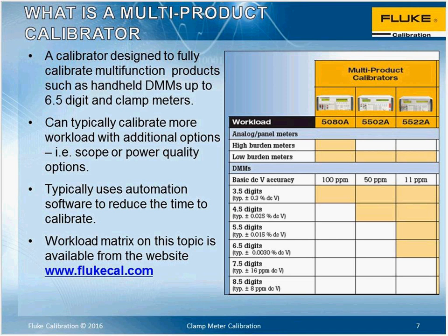Sometimes the product can be like other options, such as scope options, power quality options. The reason for this is these multi-product calibrators realize that if you're going to buy a product that has that many functions to calibrate DMMs, other related products have some of the same functionality but a different twist, such as energy meters or power quality analyzers. If you could just expand the functionality a bit, you could add tremendous value to your laboratory. So typically with multi-product calibrators, you'll find additional options that you can equip the product with.